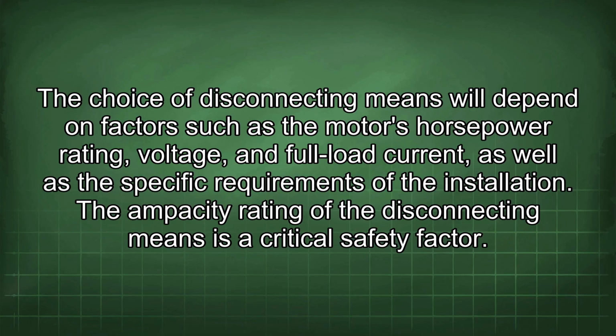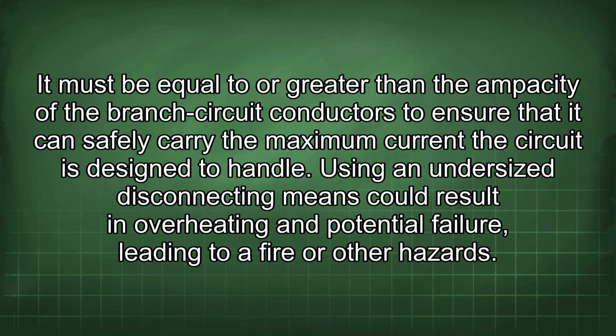The ampacity rating of the disconnecting means is a critical safety factor. It must be equal to or greater than the ampacity of the branch circuit conductors to ensure that it can safely carry the maximum current the circuit is designed to handle. Using an undersized disconnecting means could result in overheating and potential failure, leading to a fire or other hazards.